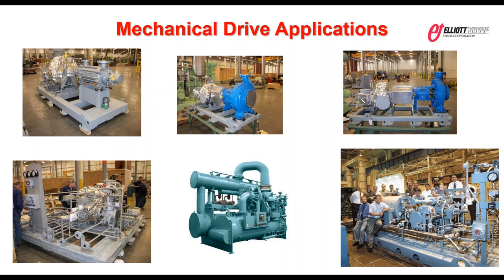I mentioned earlier about different mechanical applications as well. A lot of users might run pumps or compressors or blowers, or in this case, you see a chiller there. You don't always have to generate your own power, but you can run a mechanical device as well. So it's something else you can do for the function of dropping the pressure, but now you're driving a device where you don't need electrical motor power for that pump or for that compressor or what have you.